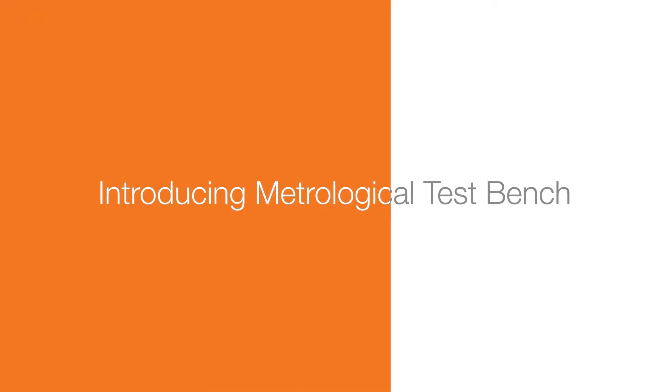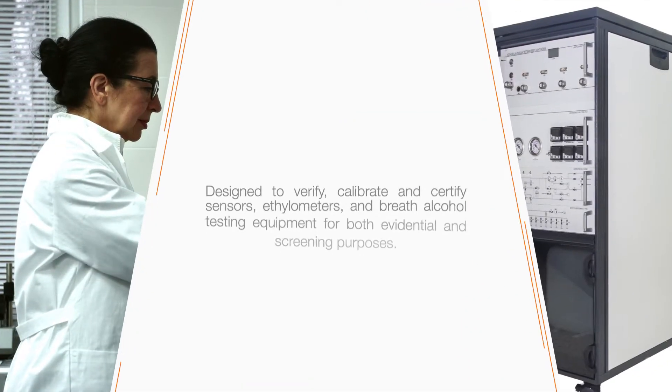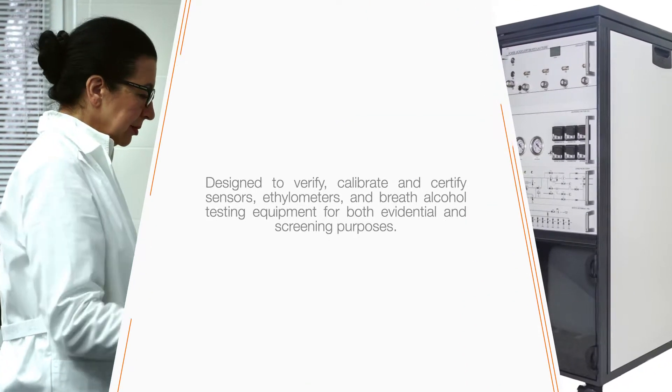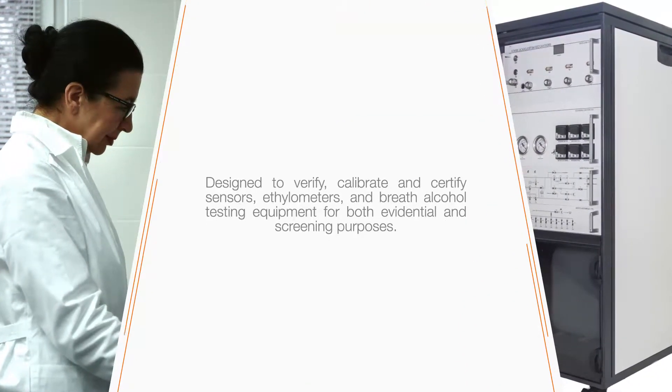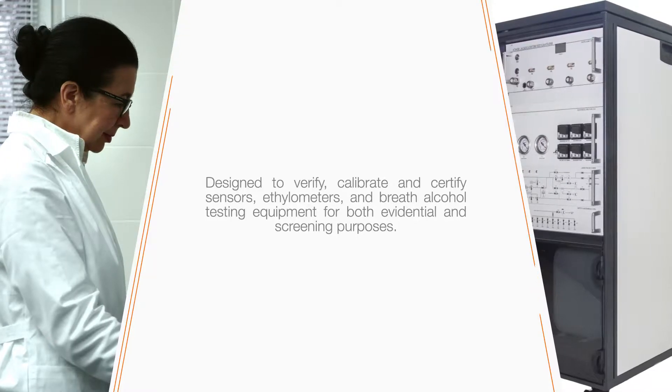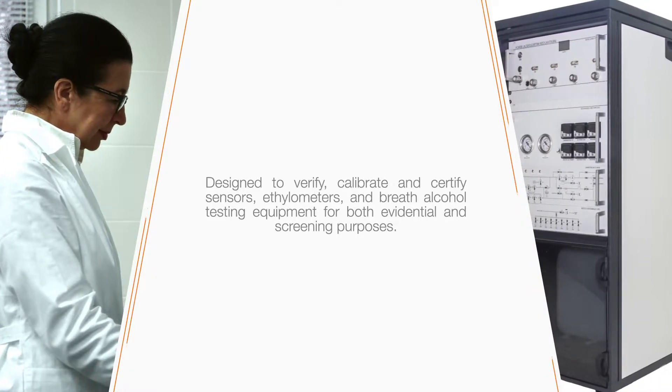The Metrological Test Bench is a highly accurate human breath simulator designed to verify, calibrate, and certify breath alcohol testing equipment for both evidential and screening purposes.